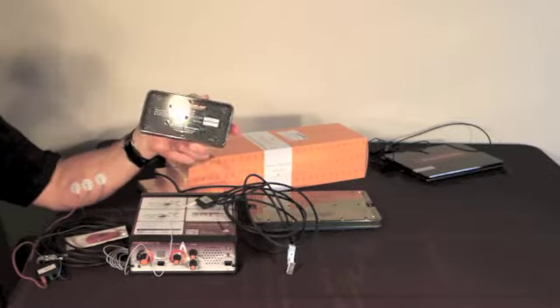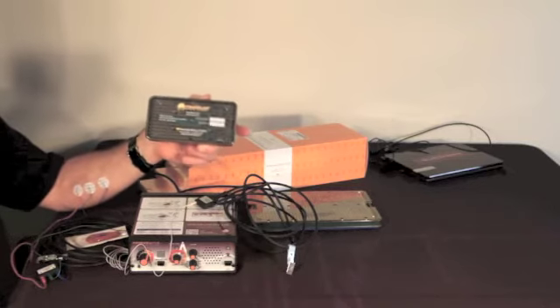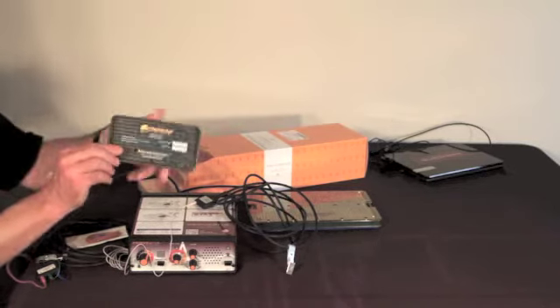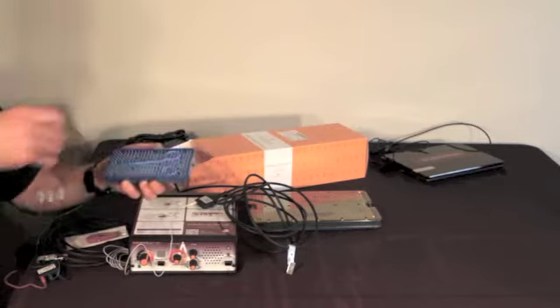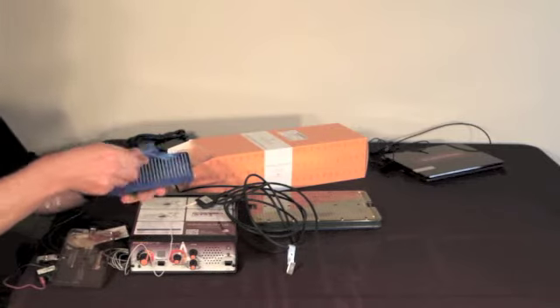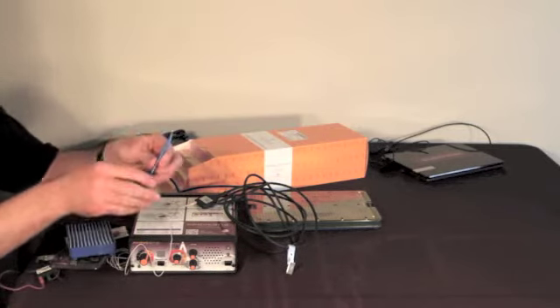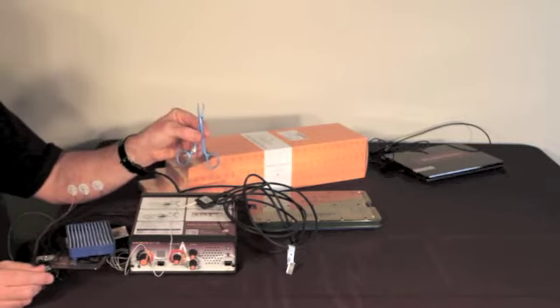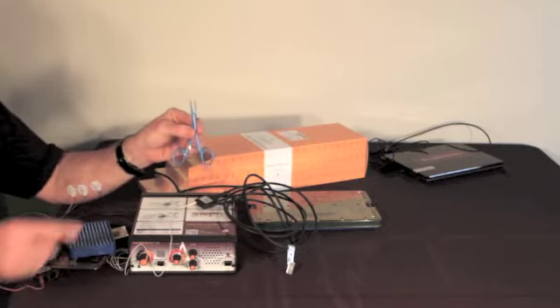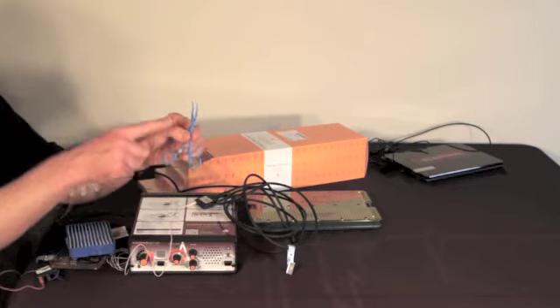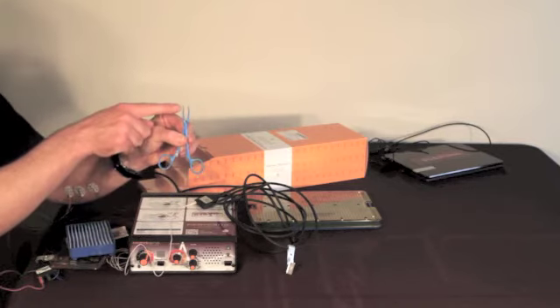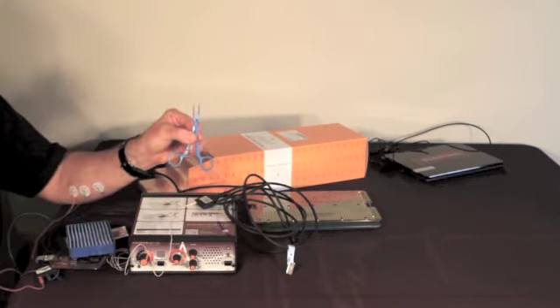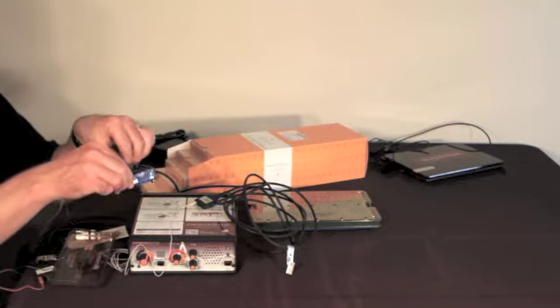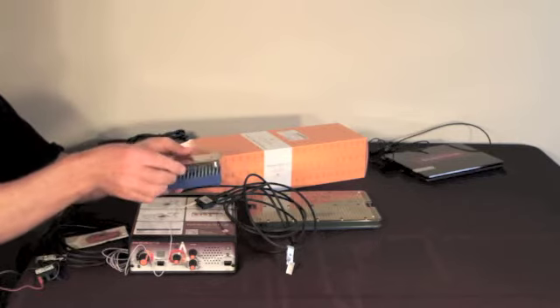With that said, it's time to discuss the stimulator probe and that final connection to have the Nerveana ready for surgery. The Nerveana utilizes reusable, modified probes. Forceps, actually, they're modified to be a probe, and they have a metal post, and they have a blue insulation, and then they have exposed tips that deliver stimulation, exposed metal. This needs to be sterilized prior to the surgery.